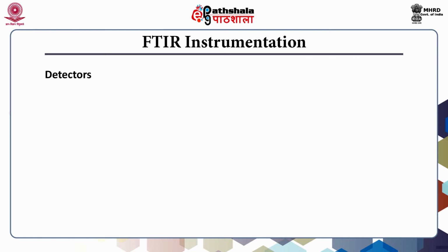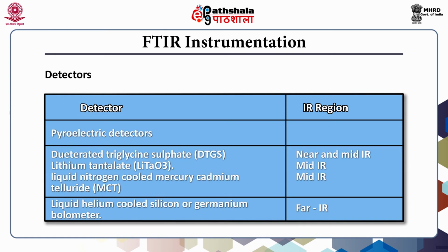For mid infrared, pyroelectric detectors are used. These detectors respond to changes in temperature, which results from the fall of radiation of different intensities. These detectors contain deuterated triglycine sulfate, referred to as DTGS, or lithium tantalate, that is LiTaO3. The detector works at room temperature. The time of scan is a few seconds.